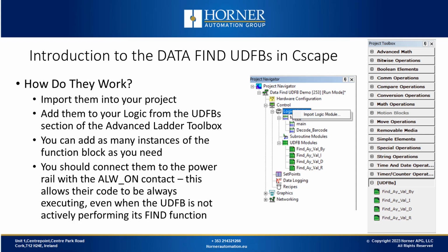Once they're imported, they will show up in the project toolbox under the UDFB section, where you can select and drag them into your logic editing area to add them to your project. We recommend with the UDFBs that we create that you connect them to the always-on contact that's connected to the power rail, so that they're always receiving power even when they're not enabled to perform their function. That way, they can perform whatever kind of initialization that they may need before they're called to action.